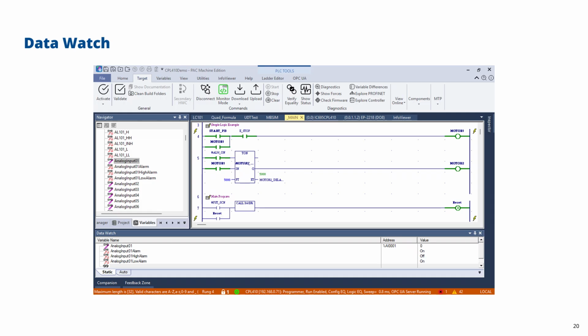Now the other thing you can do is go into the project tab and scroll up to data watch, right click on the data watch node and create a new data watch, and then double click on that data watch and it will appear in the data watch list here. And then again you can drag and drop variables into that new data watch in the same way as you use the static data watch. So that's brilliant and ideal for things like your PID loop tuning, where you want to see a few PID values. Maybe you want to configure a particular portion of the machine and you've got a combination of discrete and analog values, so it lets you see and control all of those.